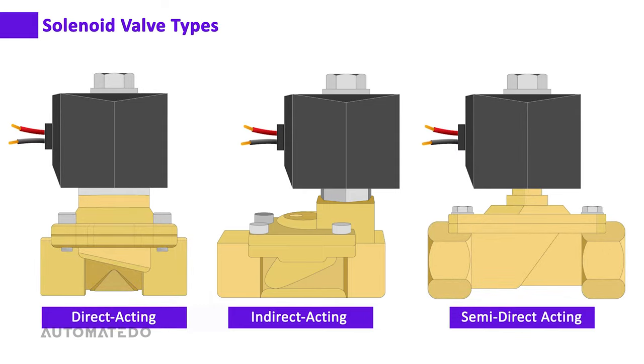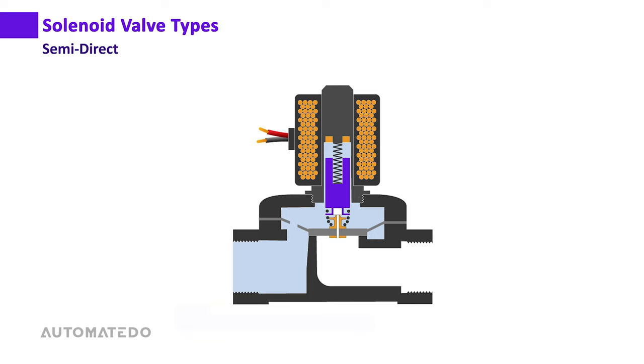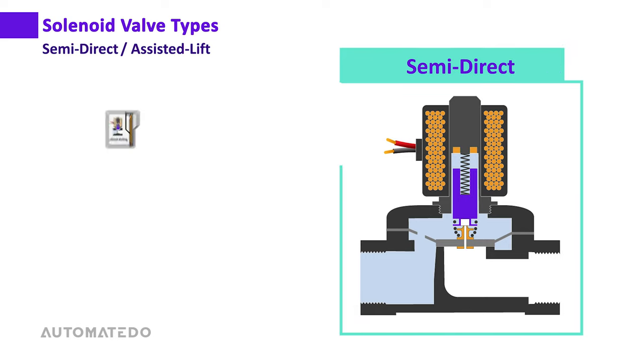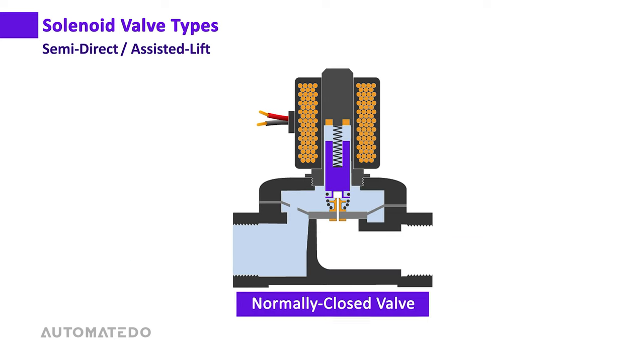Next, we consider the semi-direct acting, or assisted lift, solenoid valve. It consists of coil winding, armature, spring, plunger, orifice, diaphragm, and valve body. This valve combines the characteristics of both direct and indirect valves, with the key difference that the plunger is attached directly to the diaphragm.